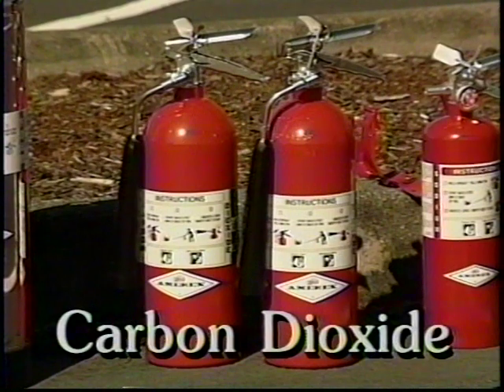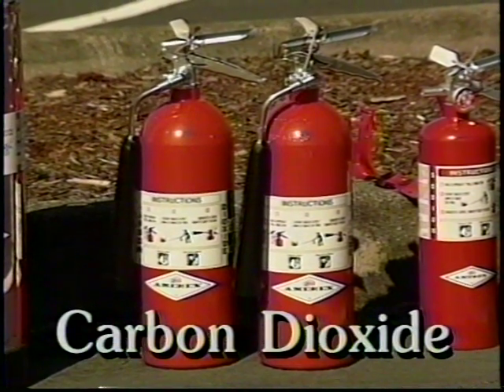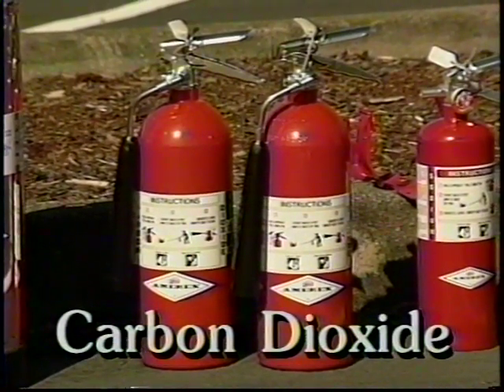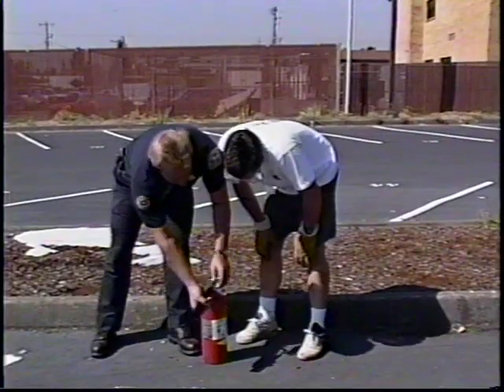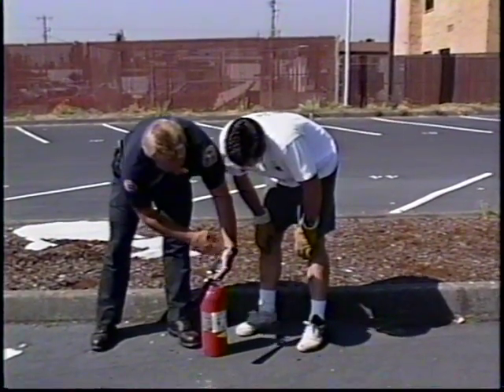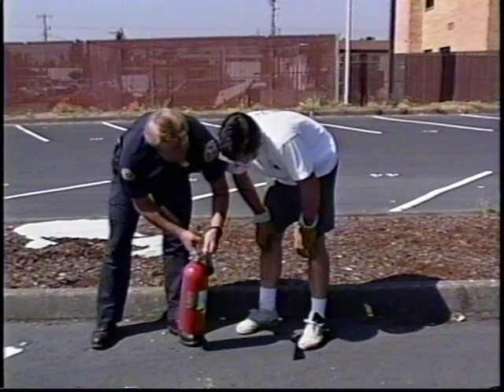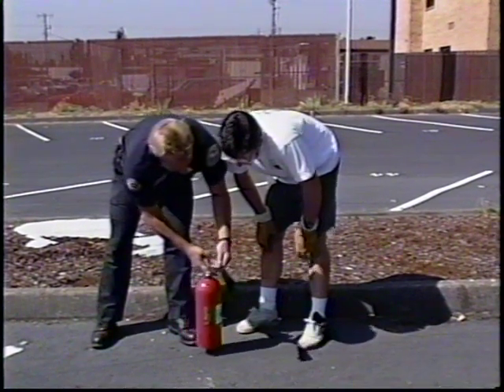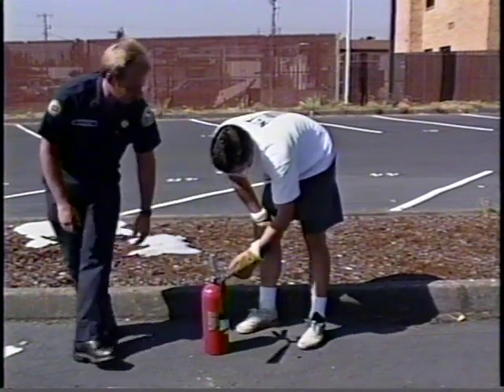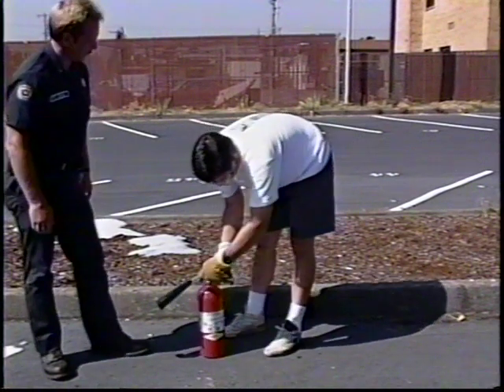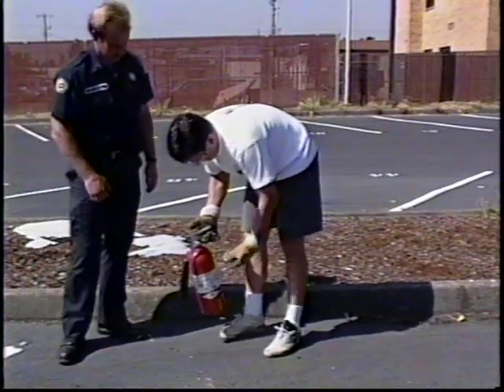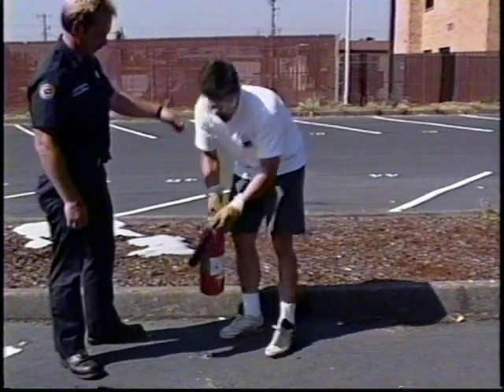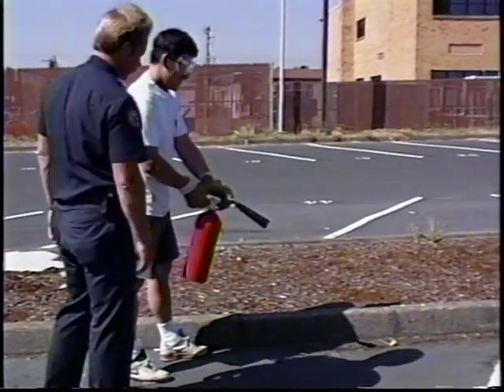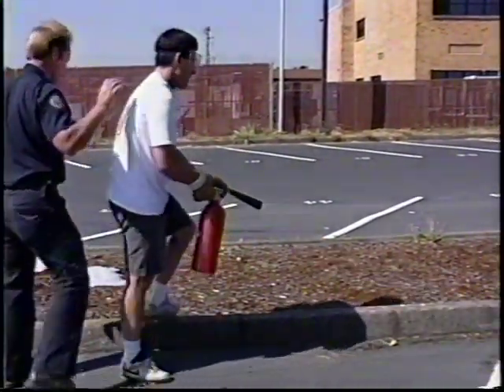Carbon dioxide extinguishers are effective with Class B and Class C fires. The discharge is a gas that smothers the fire, taking away the oxygen that is needed for combustion. To use a carbon dioxide extinguisher, carry it to the location of the fire, holding the top handle. Prepare to squeeze the shutoff handle while pointing the discharge horn at the base of the fire.